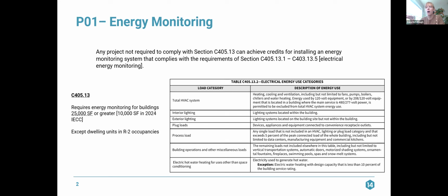The end uses that are required to be monitored are the total HVAC system. So heating, cooling, and ventilation, including fans, pumps, electric boilers, chillers, and water heating. You can exclude 120 volt equipment where your main coming into the building is 480 volt power. So those little one-off unit heaters or little transfer fans that you have don't need to be included in your total HVAC system monitoring.